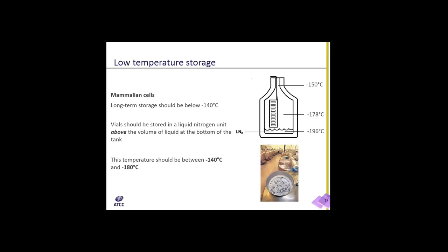There are two basic types of liquid nitrogen storage practices. One is immersing the vials directly in the liquid. The other involves holding the vials in the vapor phase above the liquid. Vapor phase systems create a vertical temperature gradient within the container. At the bottom, the liquid nitrogen will maintain a temperature of around minus 196 degrees Celsius. The temperature of the vapor phase decreases as it reaches the top portion of the container. Enough liquid should be used to guarantee that the warmest part of the container at the top is always at a temperature at or under minus 140 degrees Celsius. It is highly recommended that vials be stored in the vapor phase rather than the liquid. Since metabolic activity is arrested at minus 140 degrees, the additional cold temperatures of the liquid phase offers no real advantage. However, immersing material in the liquid phase runs the risk that some of the liquid nitrogen could penetrate and damage the plastic vials.